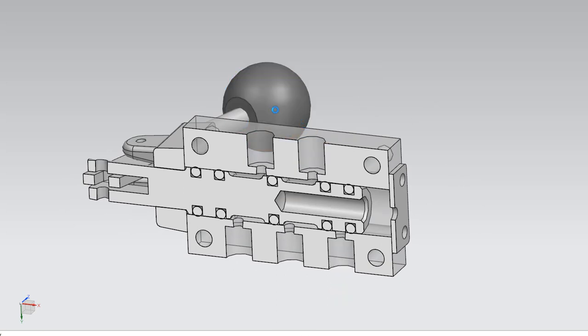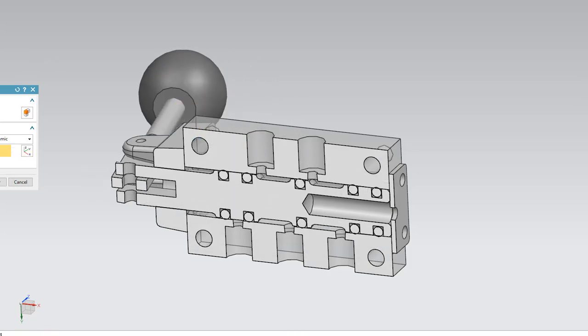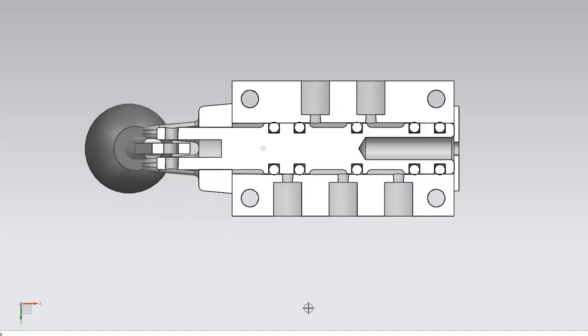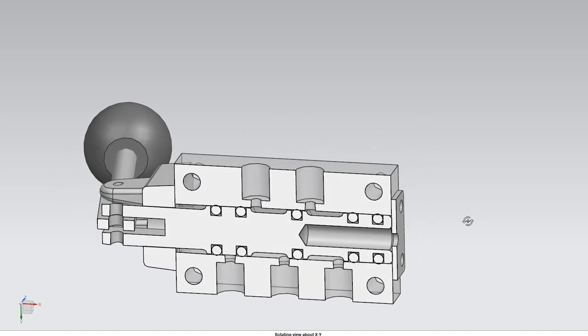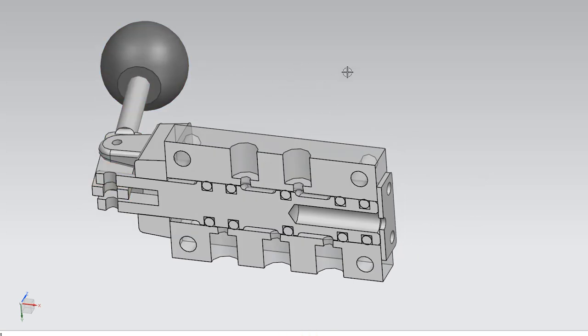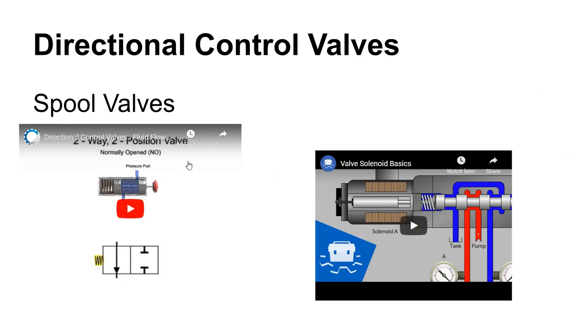With the spool shifted to the other position, pressure goes to A — extending the cylinder — and the B side drains to the tank. Those are the two positions: pressurizing A or pressurizing B. The hand lever is one way to do this; a lot of control valves use solenoids to push the valve in one direction, with a spring returning it or a solenoid on the other side returning it.